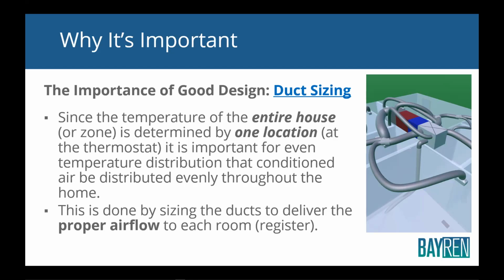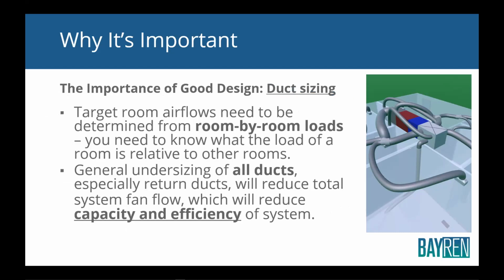So for example, the load on the master bedroom might be 10% of the total cooling load. And what that means is, in order to have even temperatures, if the load is 10%, it needs to get 10% of the airflow. So if your system is moving 1,000 CFM, 10% is 100 CFM, you need to make sure that the master bedroom gets 100 CFM in order to have good proper airflow for each room. Okay, so that's how duct sizing works, and that's what Manual D is all about. The target airflows need to be determined by room loads.